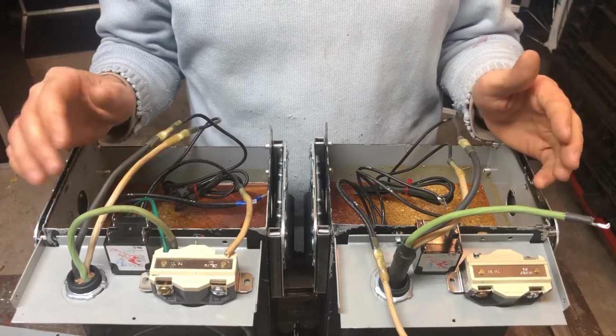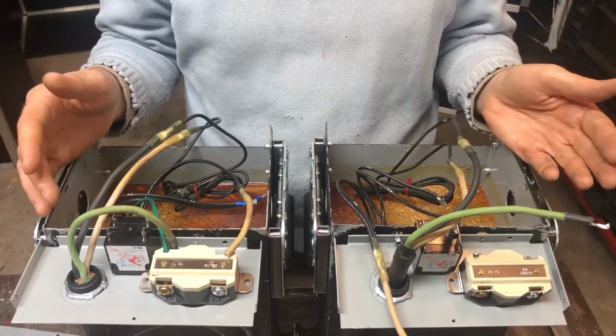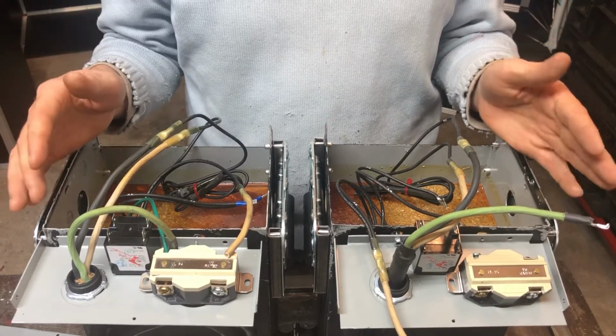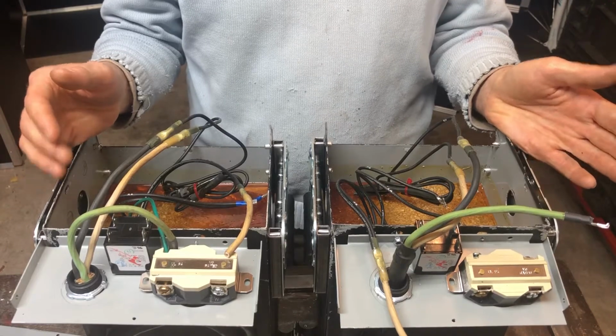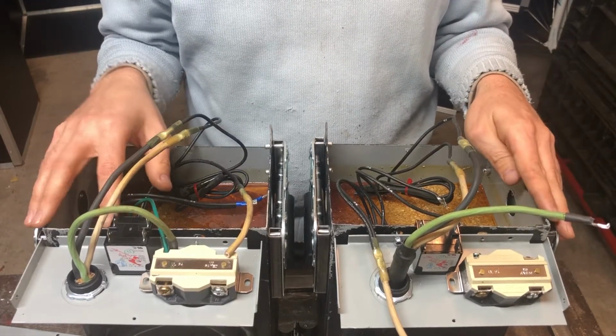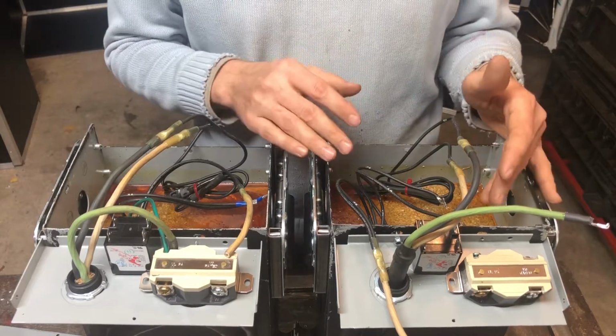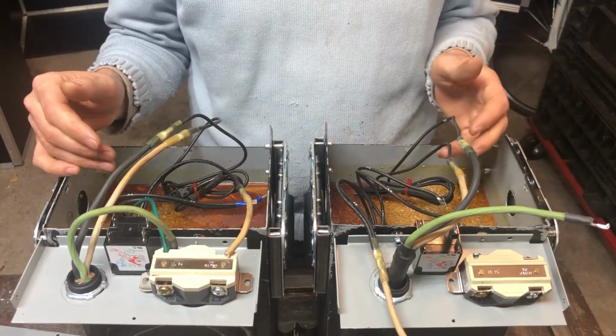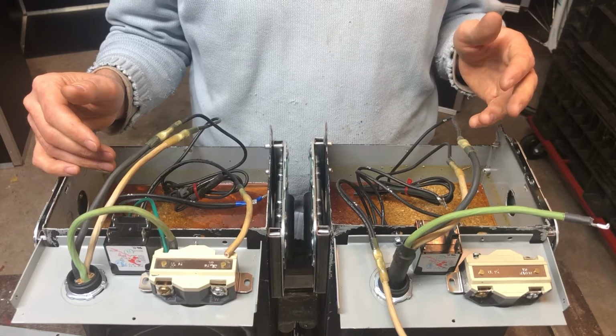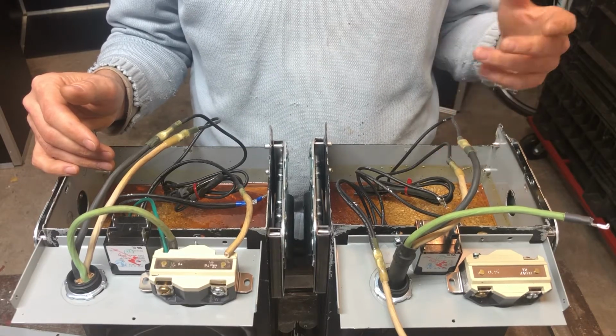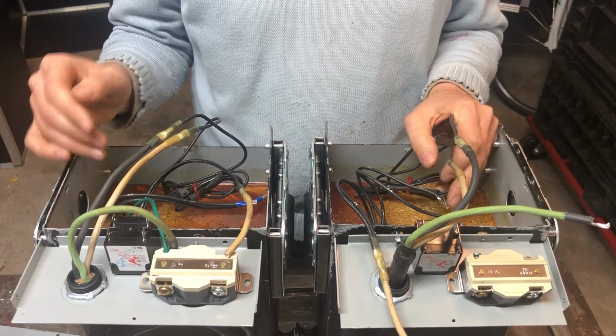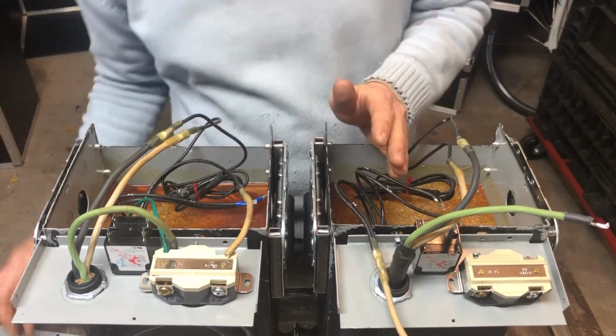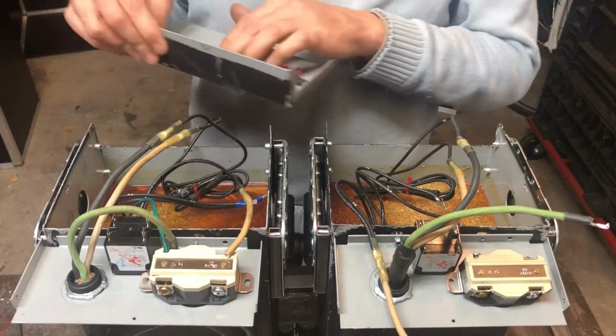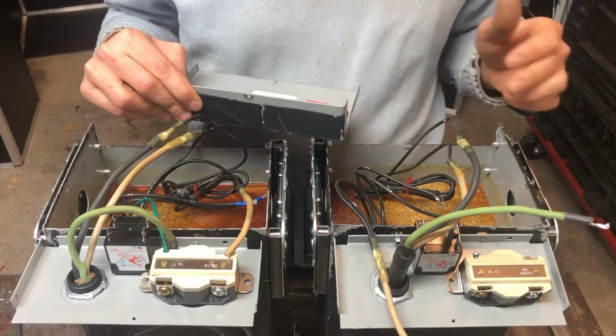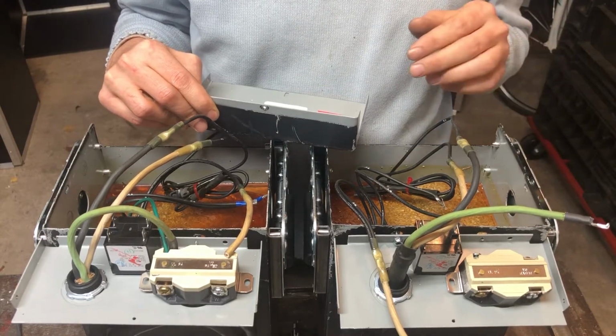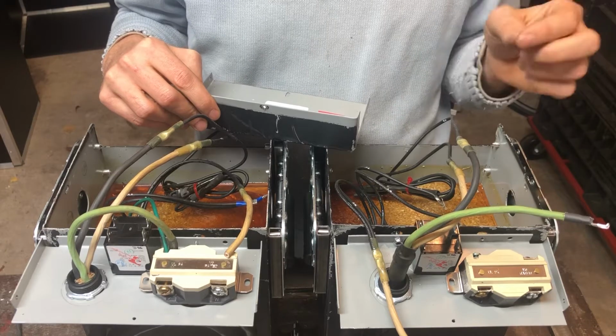So in order to complete our show, we have to have access to that power. So I purchased used on eBay these 5 kVA transformers. They're multi-tap input and output, so I can have 120 volts, 240, 208, and 277 as an input. And then as an output, let me see here, I can have 120, 240, or 240/120 with a center tap.